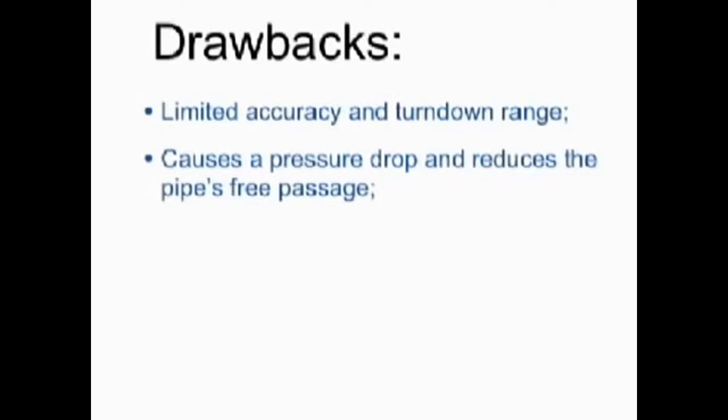Of course, there are drawbacks too. It has limited accuracy and turndown range. If high precision is your primary objective, there are probably better technologies. The orifice causes a pressure drop and reduces the pipe's free passage. As sensor technologies go, this is one of the more invasive.